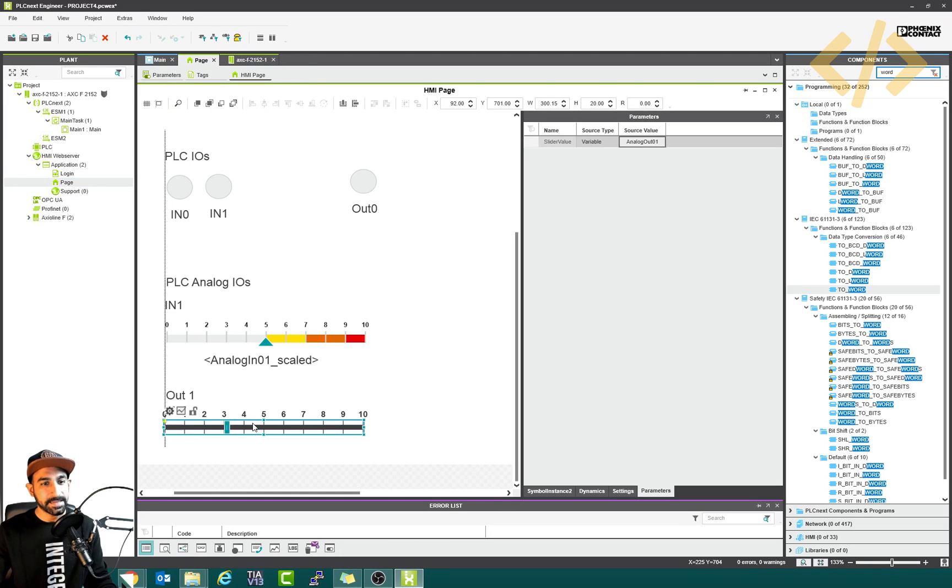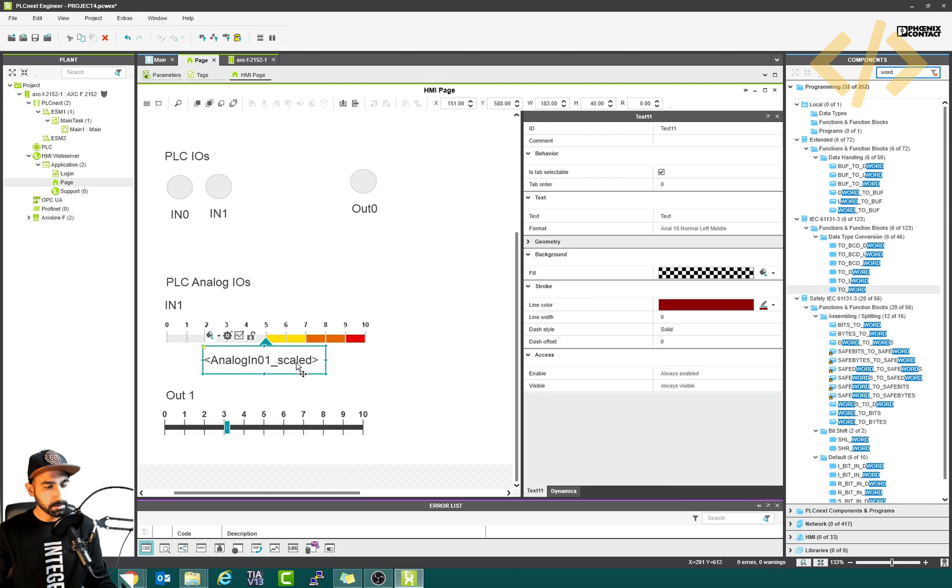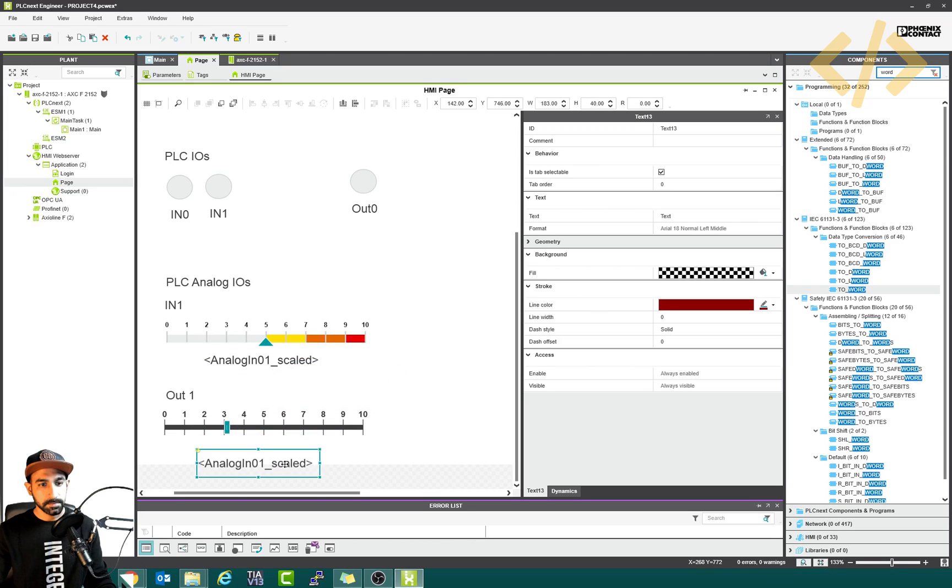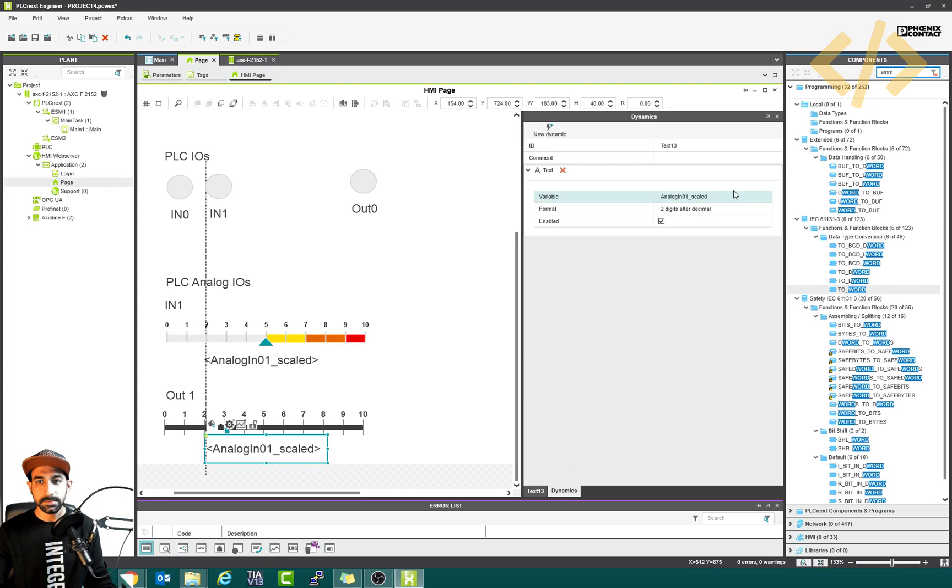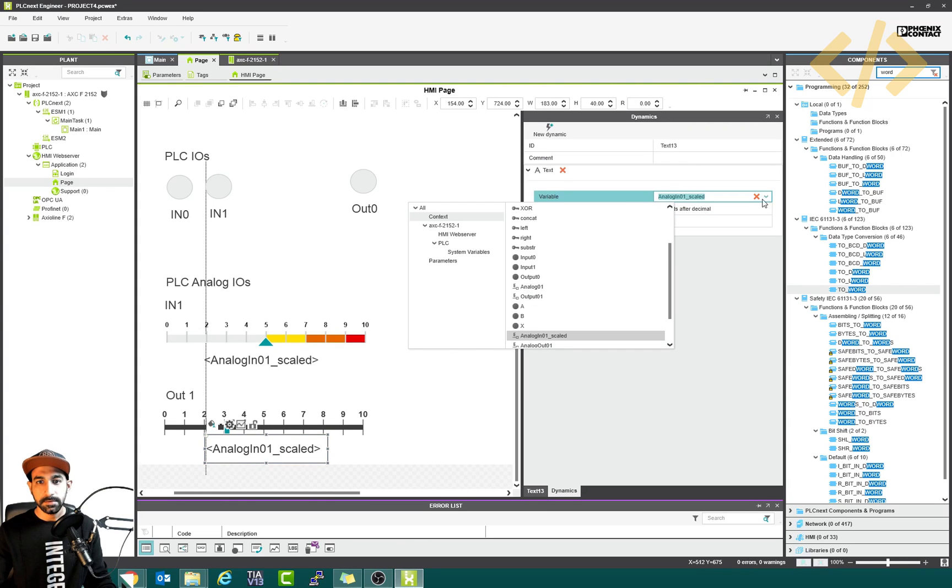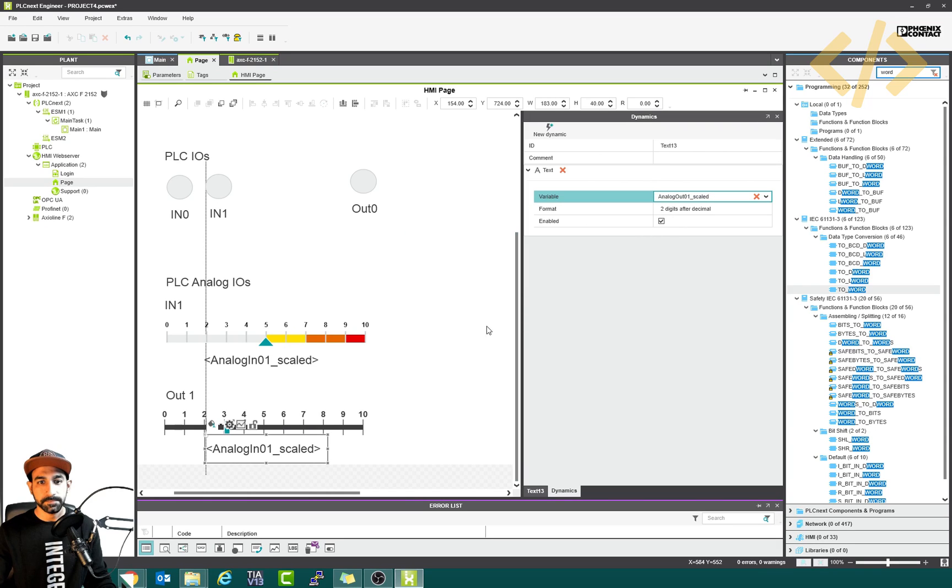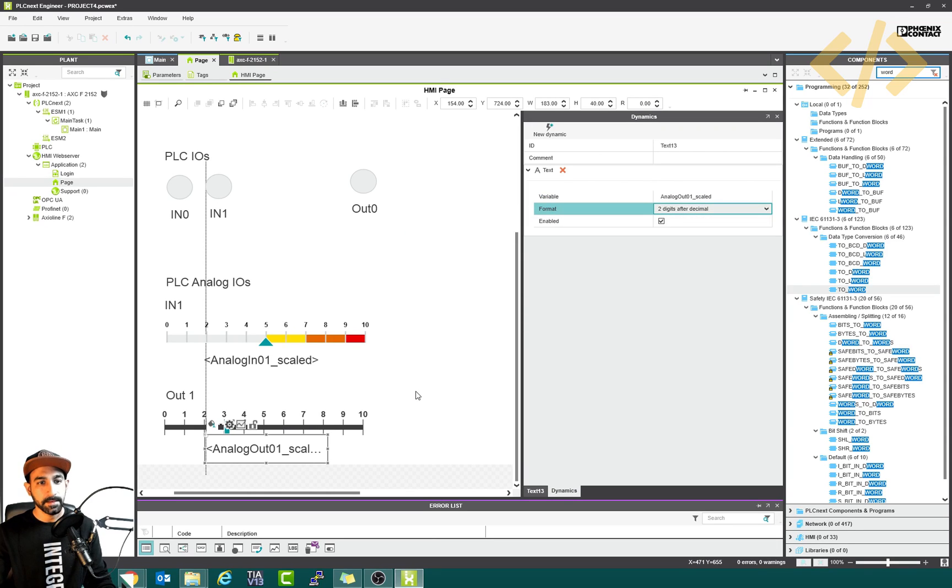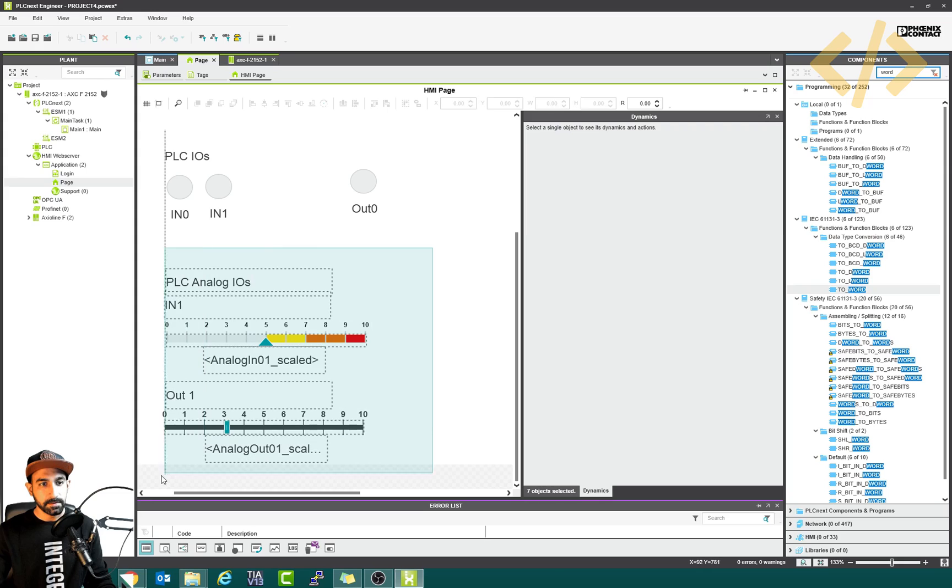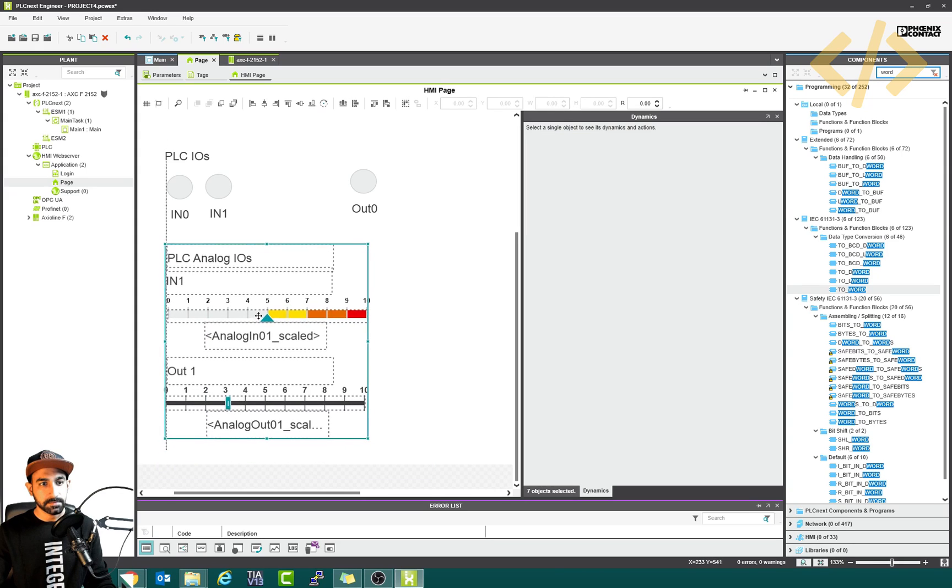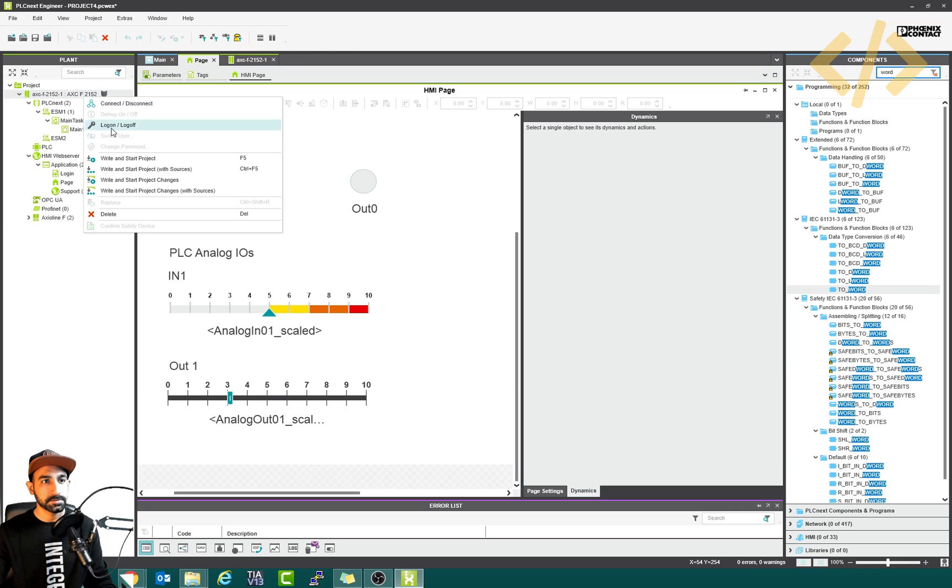So I go back to my page again. So this value is getting inside the PLC, getting it scaled and then coming out. So I will copy this variable, bring it here. Change the variable. The dynamics, analog out scale. That's it. Press enter. So this is defined here. Now let's just bring it to the top and let's try to download.